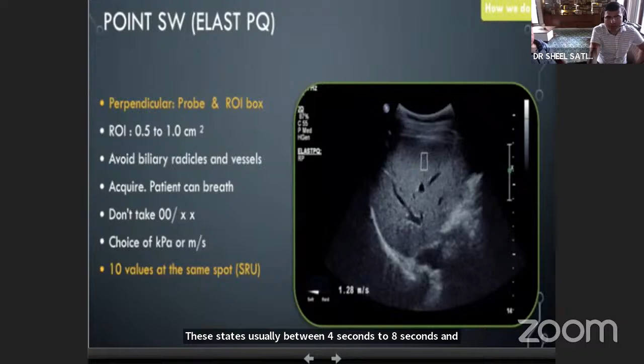Yes, the reason the patient is asked to hold breath is that once you enable the shear wave from the switch, at that specific time the tissue should not be moving. You fire the impulses and you allow it to come back. This usually takes between 4 seconds to 8 seconds, and that's very important. The patient should hold the breath.